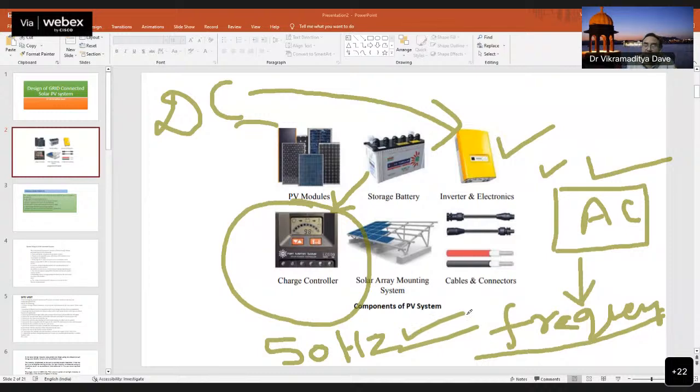Moreover, later on I will also discuss that the grid is to be provided with a sensor, so that as soon as the grid supply goes off, जब हमारी लाइट चली जाती है तो सोलर हालांकि जनरेट कर रहा है लेकिन ग्रिड को वो सप्लाई बंद कर दे. अब आप पूछोगे सर ग्रिड को सप्लाई क्यों बंद कर दे, हमें तो जरूरत पड़ती है, लेकिन ये प्रोटेक्शन सिस्टम है. यदि ग्रिड बंद हो गया और सोलर ने अपना फीड करना शुरू कर दिया तो रिवर्स में आपकी सप्लाई चालू हो गई. और अगर मान लो ग्रिड पे कोई काम कर रहा है कोई व्यक्ति, तो वो सोलर ने जो सप्लाई दी है वो उसके बॉडी को टच हो जाएगी and he will be no more. So it can be a fatal accident if the solar continues in case the grid becomes off.